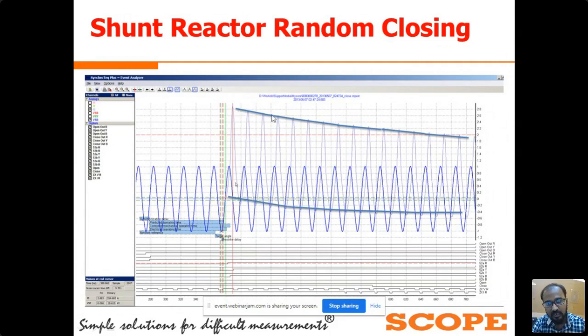So after a few milliseconds the current goes to natural, and after a few milliseconds it will flow symmetrically, the same in the positive side and the same in the negative side. So we can see here, at the time of closing of the shunt reactor, if the current starts to flow near the 0 point, there is a chance of a starting current of more than 3 to 4 times the full load current.